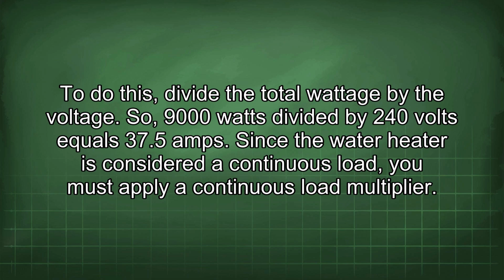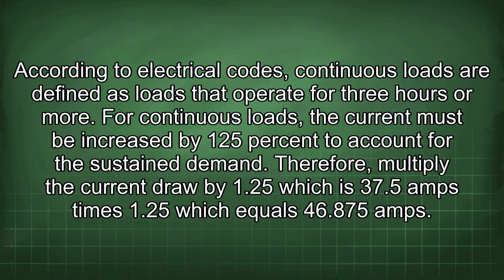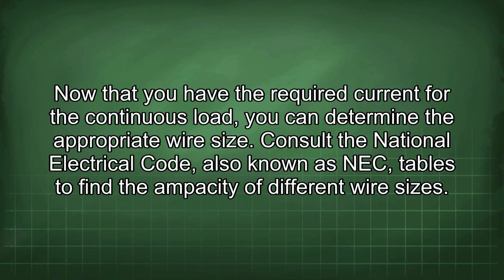Since the water heater is considered a continuous load, you must apply a continuous load multiplier. According to electrical codes, continuous loads are defined as loads that operate for 3 hours or more. For continuous loads, the current must be increased by 125% to account for the sustained demand. Therefore, multiply the current draw by 1.25, which is 37.5 amps times 1.25, which equals 46.875 amps. Now that you have the required current for the continuous load, you can determine the appropriate wire size.